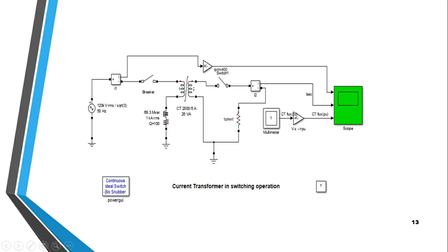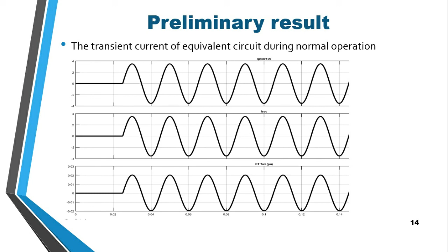Next, I will show my preliminary result of the simulation of transient current for both normal and switching operation. This is the result from normal operation: the first graph is for primary current, the second graph is for secondary current, and the last graph is for the CT flux.